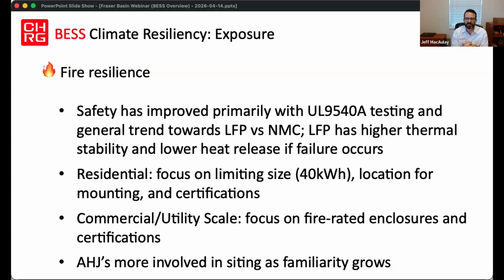Commercial and utility scale has the same certification, 9540, just slightly different rules in the way that it's applied in the code. Traditionally, it's just a lot easier to have these in full storage or shipping containers. They're fire rated enclosures, and at certain applications need to have a certain fire rating, 1 hour or 2 hour burn, where if you had a forest fire around it, it's going to take a certain duration before it penetrates the actual enclosure it's in. The 9540 cert applies for these applications as well.